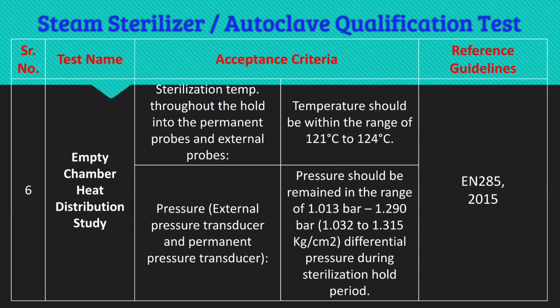Pressure measured by external and permanent pressure transducers should remain in the range of 1.013 bar to 1.290 bar; the pressure criteria depends on developmental studies and the finalized recipe. The reference guideline is EN 285:2015. The sterilization hold time in permanent and external probes should be not less than the hold time decided during cycle development — generally not less than 15 minutes as per EN 285.